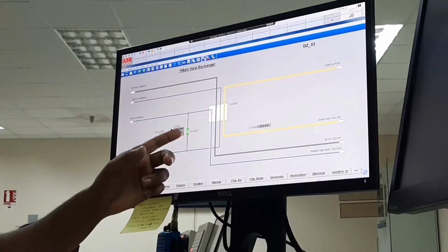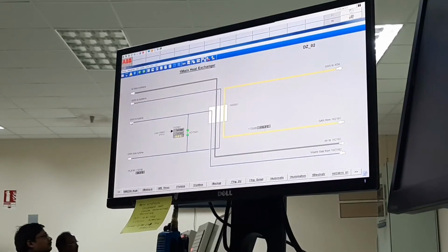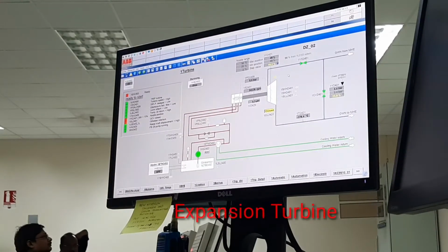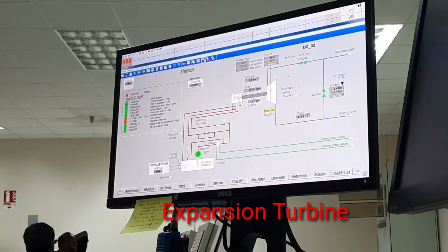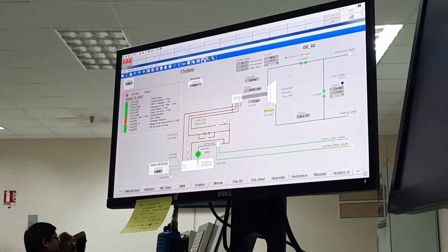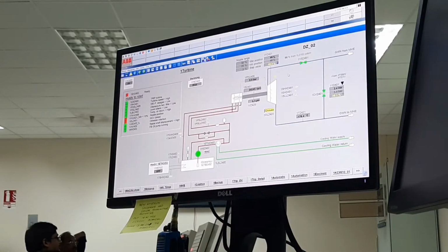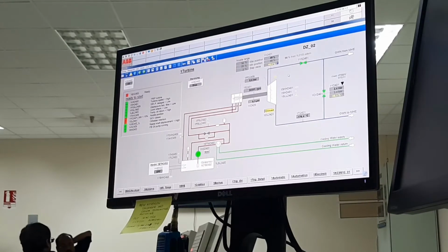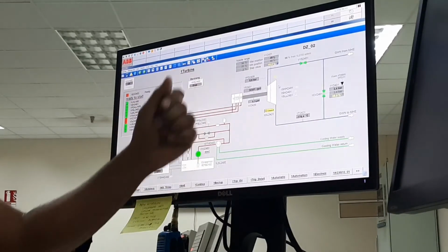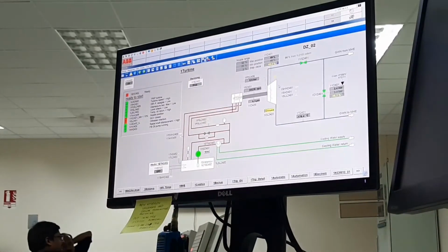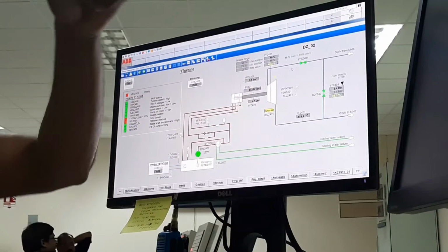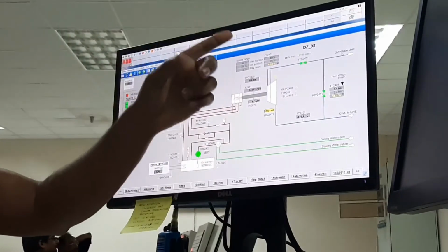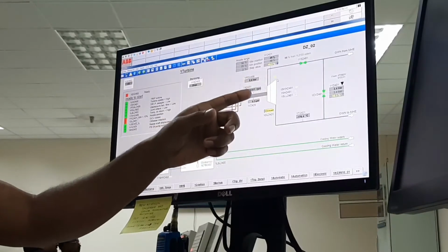So where will this product go? Turbine. The expansion turbine. The expansion turbine is a very small turbine, like this. We don't see it; it is inside the box. But the turbine RPM is very high, 44,500. If it is moving, you cannot see whether it is moving or steady; it moves very quickly, the speed is very high. So for this expansion turbine, we are using RPM 44,500, and we are using an inlet pressure of 3.4 kg. So around 2000 normal meter cube of product at 3.4 kg will come into the expansion turbine.